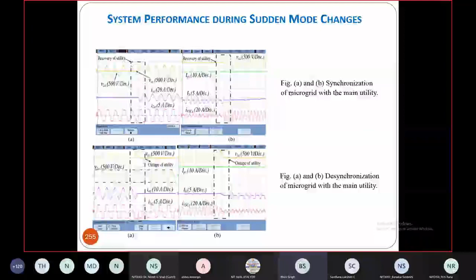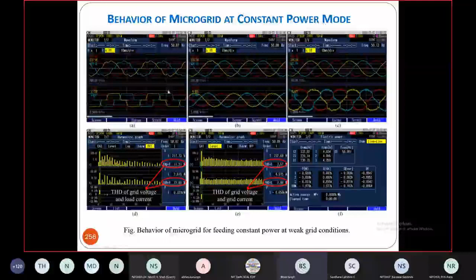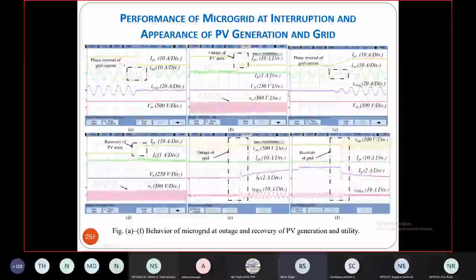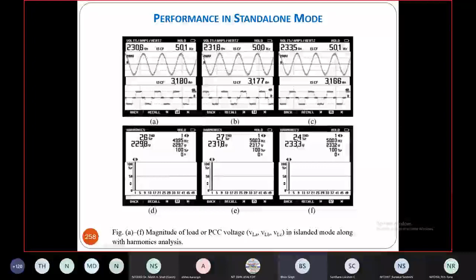Those features are typically taken care of by switching of the inverter, which also improves the voltage profile. When the load or grid voltage was distorted because of non-linear load, bringing the converter into service improves the voltage and it works well without much problem. Even with non-linear load current, in standalone mode the voltage THD is maintained around 2.4 to 2.7% across all three phases while feeding the non-linear load.